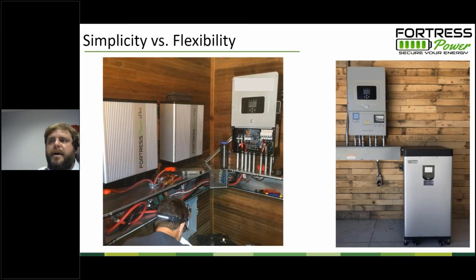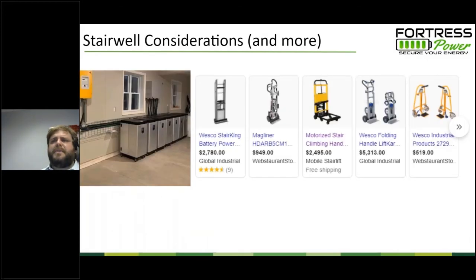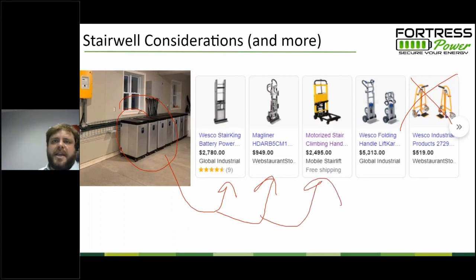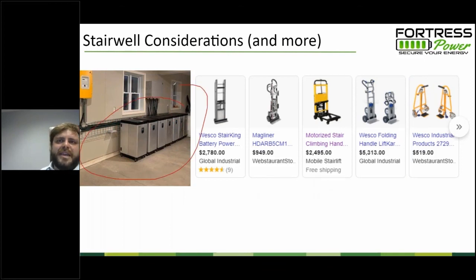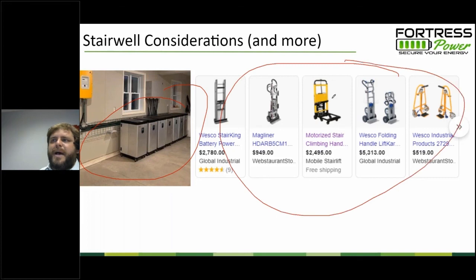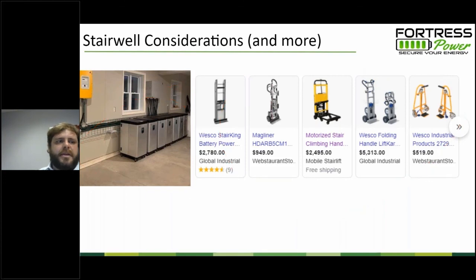More pragmatically, there's getting the eVolts down the stairs. Each eVolt weighs about 500 pounds, which is over the limit of your manual stair climber dollies. And so you get into having motorized dollies to go up and down the stairs with this heavy of an object. And maybe you're not at the point where you're ready to buy or rent a motorized dolly for your installation. If you can get all the eVolts down to the basement, it's going to be a simpler, maybe more cost-effective install, but you just might not have the ability to get the batteries to where they need to go in an easy manner. And that's where the wall mounting capability of the eFlex comes into play.